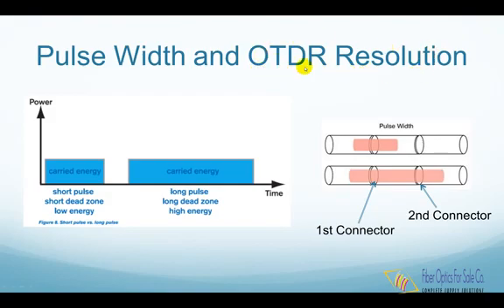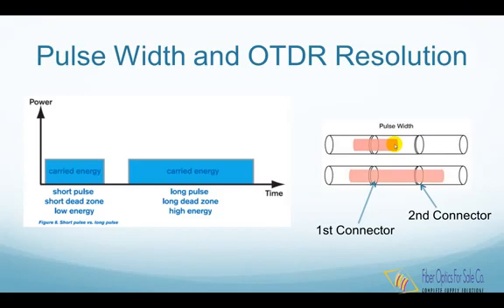The OTDR test pulse has a length in the fiber, typically 5 to 500 meters long; it cannot see features in the cable plant closer together than that. If the light pulse is too long, the pulse will be going through both events simultaneously, and the OTDR cannot distinguish these two events. This has been a problem with LANs or any cable plants with patch cables, as they disappear into the OTDR resolution. If the pulse is too short, it loses its energy before the fiber end, causing the backscattering level to drop to the noise floor, resulting in an inability to reach the end of the fiber.